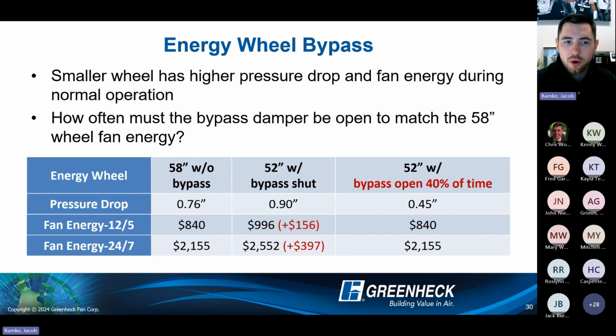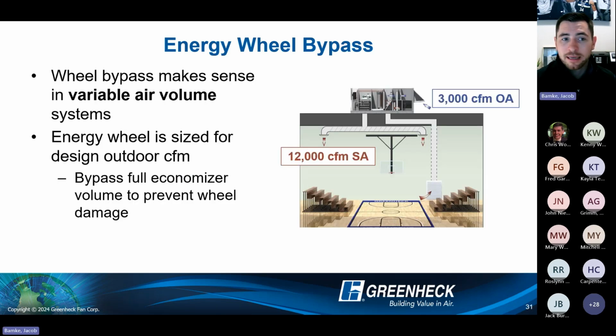So a couple things that you want to consider. Now, where does it make sense? In those VAV type applications. So in this example, we're not 100% outside air anymore. We have partial recirc. In this case, we have 12,000 CFM of supply, but we only are designed for 3,000 CFM at most during normal operation.